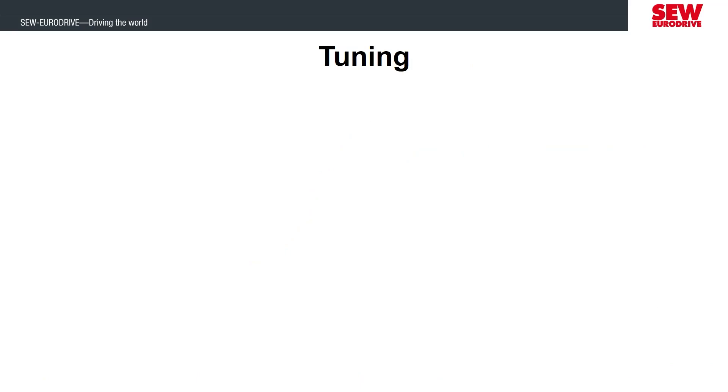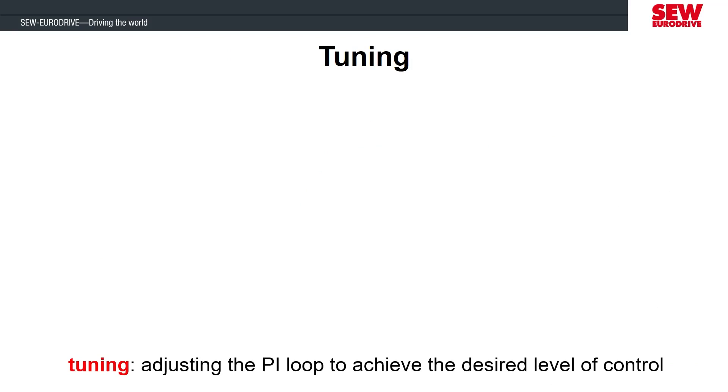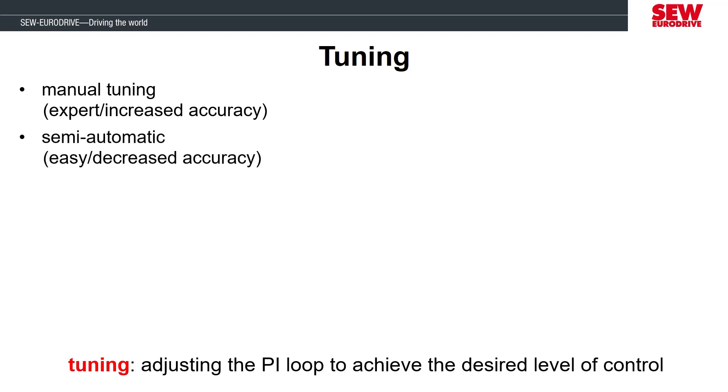There are several different ways to approach tuning the motor's performance. What we're accomplishing when we tune is adjusting the proportional integral loop to have the best response for the application. One way to tune the PI loop is to modify the parameters manually. You would need an experienced understanding of these parameters because some have precision to the thousandths of a decimal place, so small changes can have dramatic effects on the motor's performance. As you get more comfortable with the parameters, I recommend adjusting some of these manually, as this is the only way to fine tune the performance. As you're just starting to learn the MOVIDRIVE parameters, I recommend starting the tuning in a semi-automatic way, which is easier because it's only a couple of parameters you are changing, but that reduces the ability to fine tune the motor's performance.